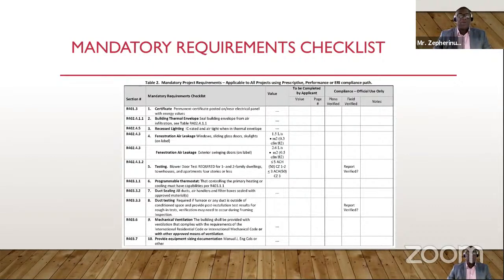So one of the new requirements is the whole question of testing the building to see how tight the envelope is. So you have to do the blower door test and the requirements in terms of the number of air changes. So you have the ACH, the requirement would be between 3 to 5 air changes per hour. The results of the blower door test should be such that you have the air change between 3 to 5 air changes per hour to demonstrate that the building is not a leaky building. And the other requirements listed here would be all the mandatory requirements for duct testing, for sealing the ducts, testing the ducts, and as well mechanical ventilation systems, the efficacy, as I said, of your fans.